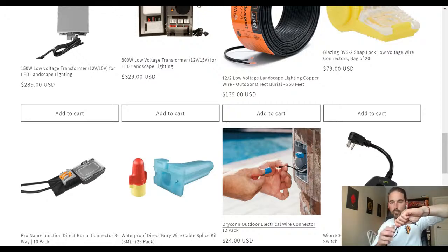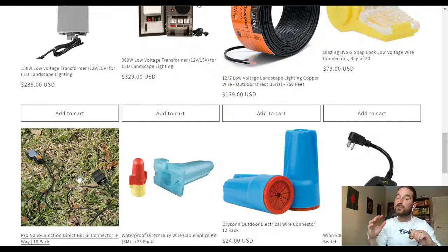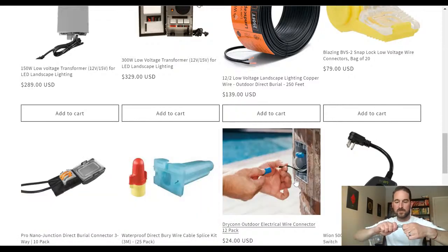I'm not taping it to keep more water out. What I want to do is make sure that I don't care how hard you pull on that now, because even with some of these that have those mechanisms, there's still a chance. It's not as likely as if you're using something like this, but there's still a chance. If you double wrap it like that, with a zip tie or tape, you're really eliminating the chance that that wire is going to get pulled out. And that's super important because that causes lots of issues.